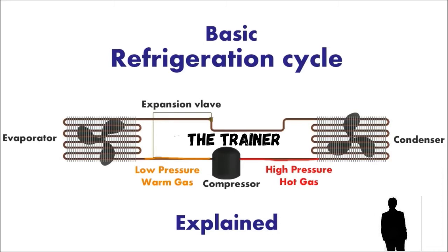And as already mentioned, for the refrigeration cycle to work, you must be able to dump heat somewhere. The air in this somewhere else needs to be cooler than the surface temperature of the pipe on the condenser. If the surface temperature of the pipe and the air around the condenser were the same temperature, you wouldn't be able to dump any heat, so you wouldn't be able to cool the room down.